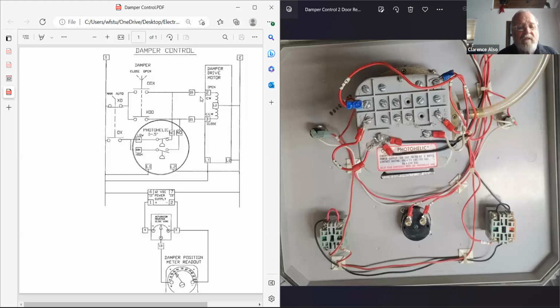And now you've got that switch up there for manual. So that's the automatic part. Here's the manual part of it. Whenever we switch into manual, notice the XO and the OX. What does that mean to us? Well, that means the top contact, when it is in manual position, happens to be closed. And if you look at the one below that contact, when in the manual position, now it's open, going to the Photohelic. So we want to have 120 volts going across that top contact.